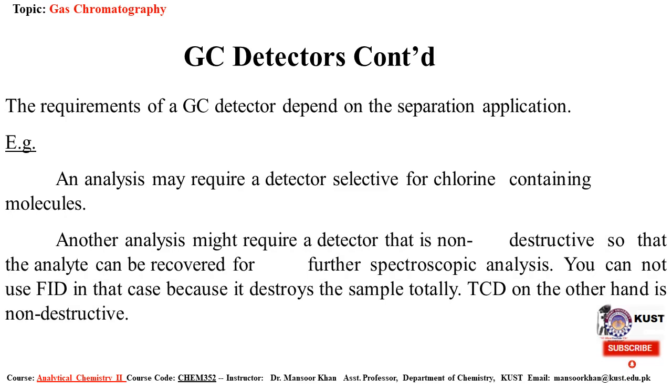Another analysis might require a detector that is non-destructive so that the analyte can be recovered for further spectroscopic analysis. You cannot use FID in that case because it destroys the sample totally. TCD, on the other hand, is non-destructive.